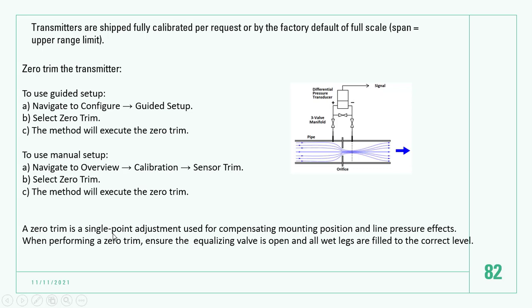Zero trim is a single point adjustment used for compensation of mounting position and line pressure effect. When performing zero trim, ensure the equalizing valve is open and all wet legs are filled to the correct level. Okay. Here equalizing valve here, equalizing valves here. Here should close, here should open. So this side and this side should be equal pressure. Okay.